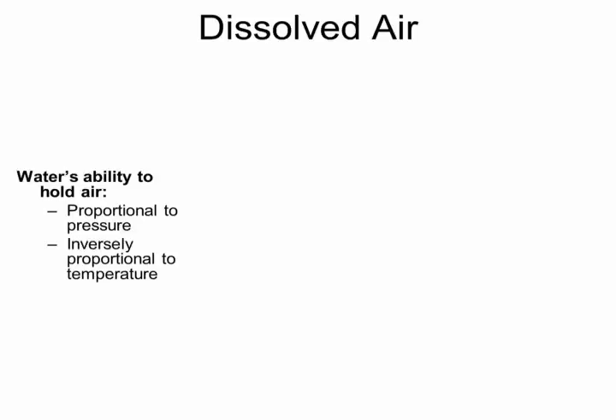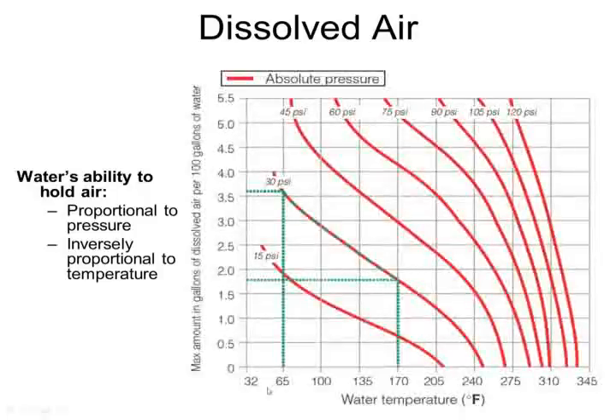The inversely proportional temperature is you basically take a pan of water, put it on your stove. You don't see any air bubbles, but you bring it up to a boil, and basically that air is coming out of solution. So with that, here is in a hydronic system how water and air react together as it relates to how much air is dissolved in that water. On the x-axis is the water temperature in your system, starting at freezing, going up to 345. And the y-axis is how much air is in your system for every 100 gallons. And these red bars are basically isopressure bars, and we'll talk about that in a second.